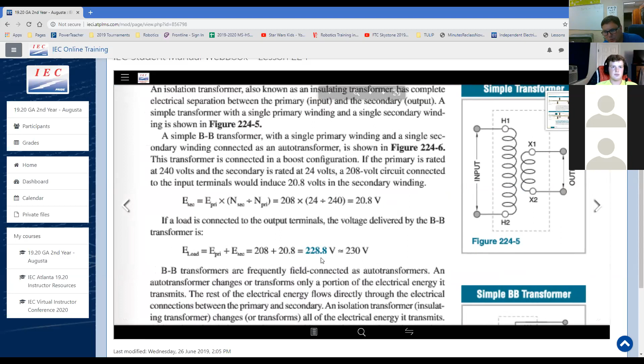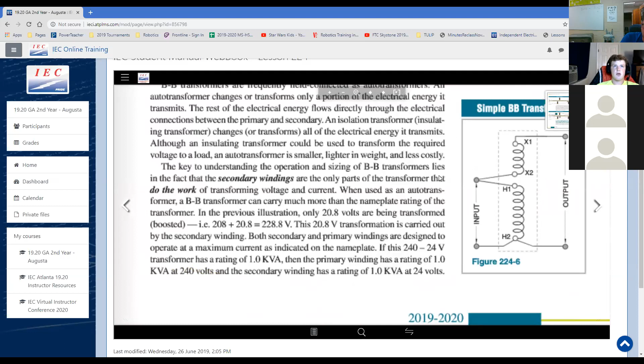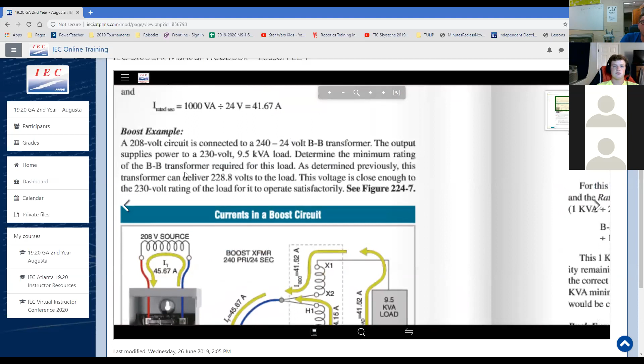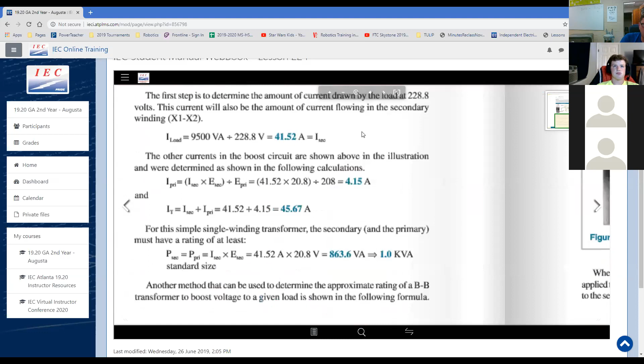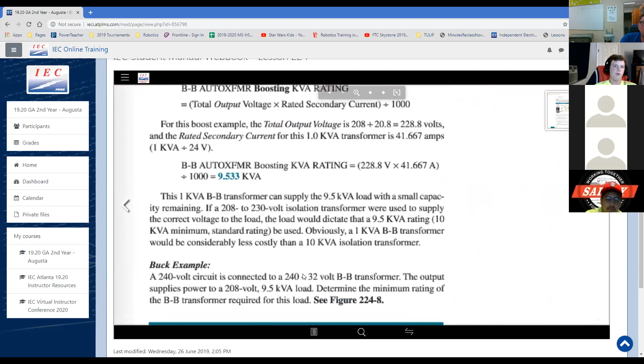So, but again, why go through all this trouble to do that? Well, this 240 and 24 volt transformer has a rating of 1 kilovolt amp, or 1 kVA, and the primary winding has a rating of 1.0 kVA at 240 volts, and the secondary winding has 1.0 kVA at 24 volts. Again, why would you do that instead of just getting another transformer? And we're gonna do the math in just a minute to get the wiring and all that situated. I wanted to show y'all. So in this situation, we're gonna go back and do the math in just a second while y'all are getting set up over there.